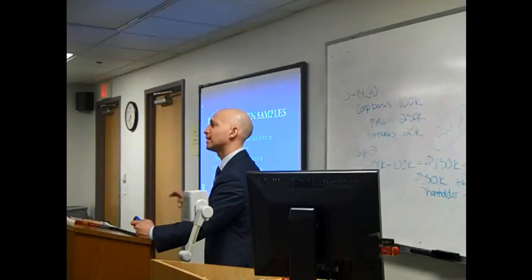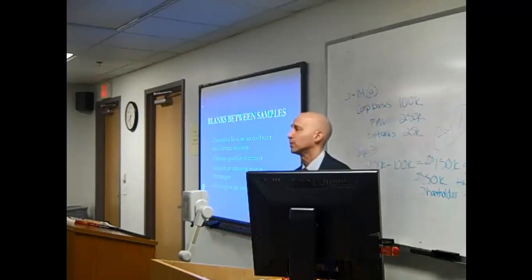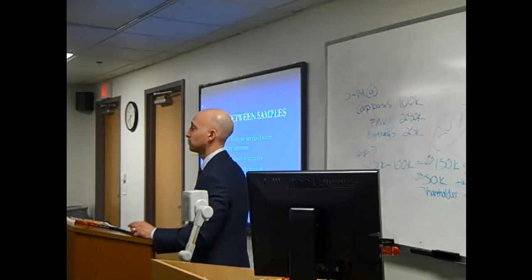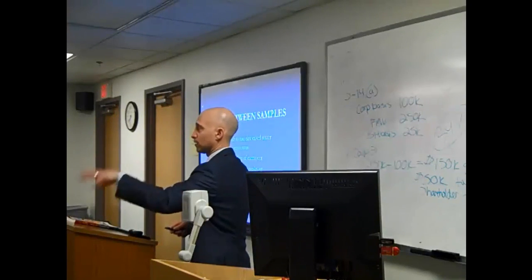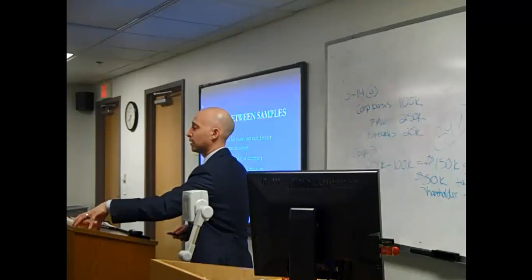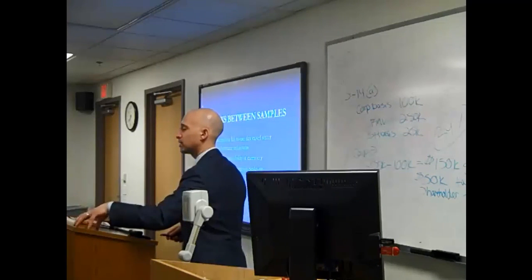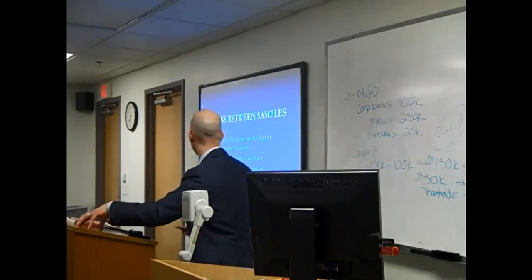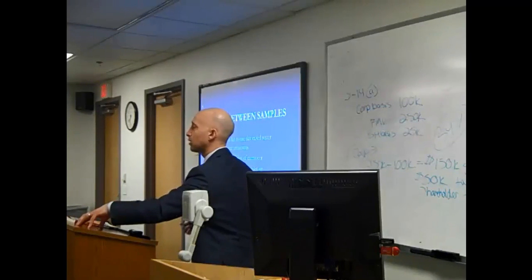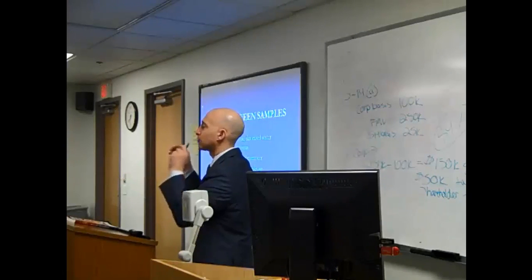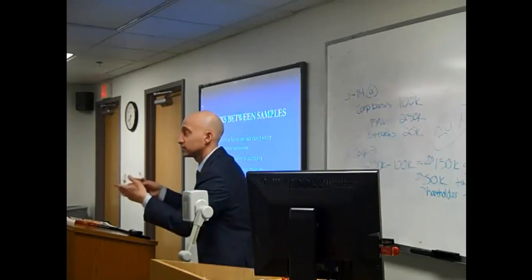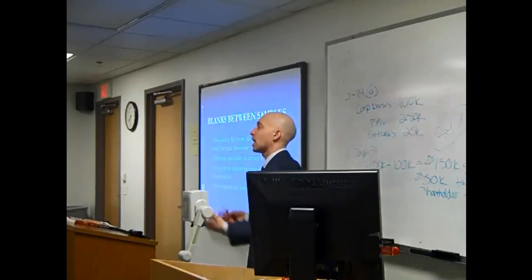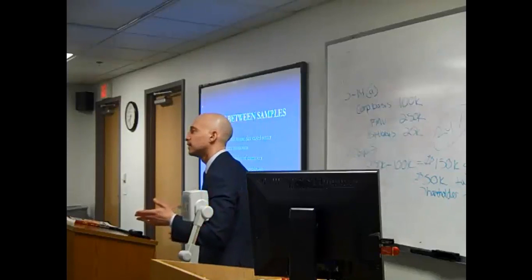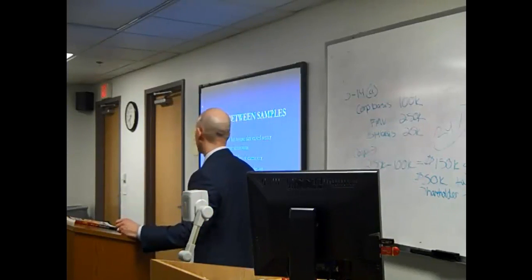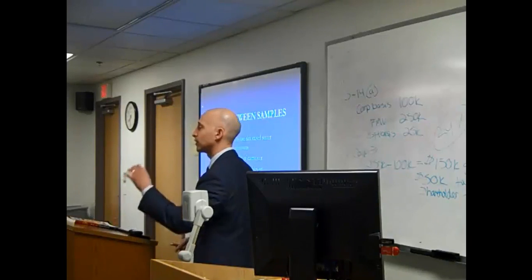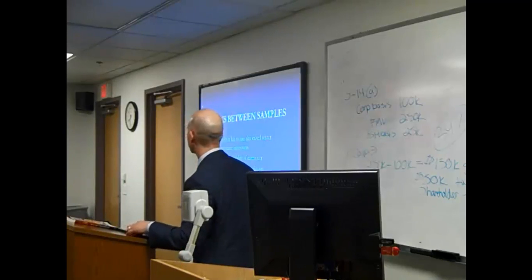Blanks. So I was talking about how to eliminate carryover, how to make sure there's no contamination. The lab should run a blank between each unknown, right? So defendant A gets tested, and then you put a blank between defendant A's blood sample and defendant B. The blank is essentially deionized water, so there should be nothing that comes out, right? And if there's carryover, then what you'll see on this blank is maybe ethanol, right? And then you know that there's some carryover. The testing process is compromised. If you don't do that, you can't prove that there's no carryover. But laboratories won't do that because it's an extra expense and it's extra time creating the blanks, typing them into the computer.